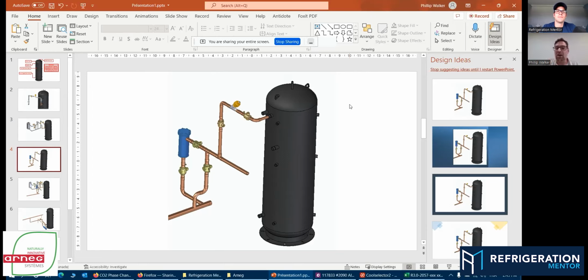And we've had a lot of success by maintaining it like that, because on a small system, what we'll typically do is have a little more flash gas in the system. So that small 20 kilowatt system will have maybe a drum a quarter of the size of this. Our mass flow is like 2,000 pounds per hour. Imagine these systems are going into your local convenience store, more or less. So that just paints a picture of how much load is on there. These little mini boosters, we call them. So this valve, to eliminate another point, instead of building redundancy on it, we put a little mechanical valve, and she works really, really nicely with a solenoid.